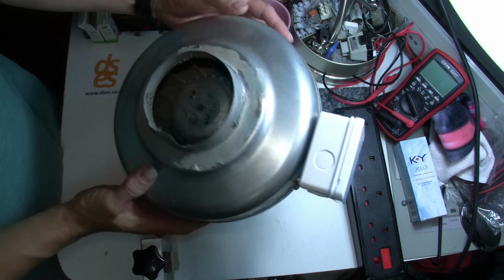Certainly the point of sale didn't mention anything about it stopping the fan by breaking the neutral path. Everyone knows you don't mess with neutral. You don't fuse neutral, you don't switch neutral, and you don't backfeed neutral, because any of these things can make something appear to be de-energized when it is in fact live on both poles.